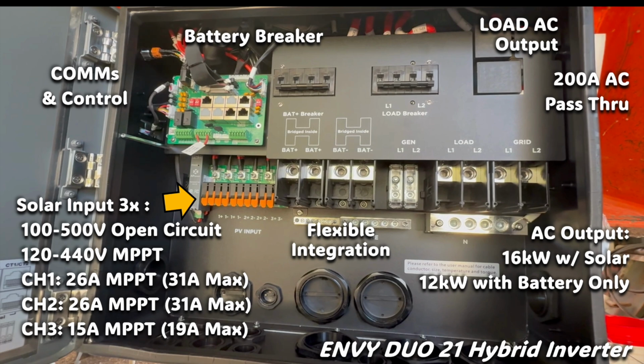First up is solar input. There are 3 maximum power point tracking channels. 1 and 2 have 2 parallel terminals each, and channel 3 has a single terminal pair. The open circuit voltage input is 100 to 500 volts DC. For maximum power point tracking voltage, 120 to 440 volts. Channel 1 has a maximum power point current of 26 amps, which is 31 amps maximum. Likewise, same for channel 2. And then channel 3 is a baby channel, 15 amps. So basically a single string of panels.